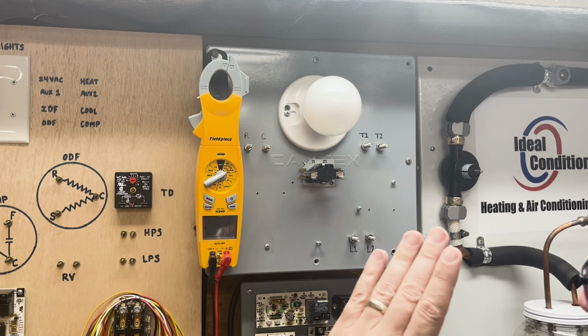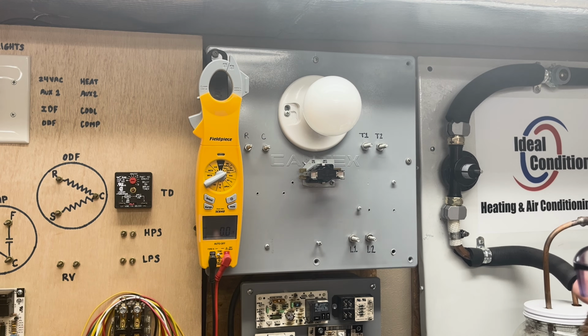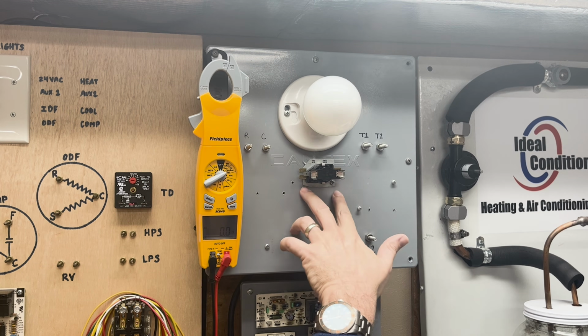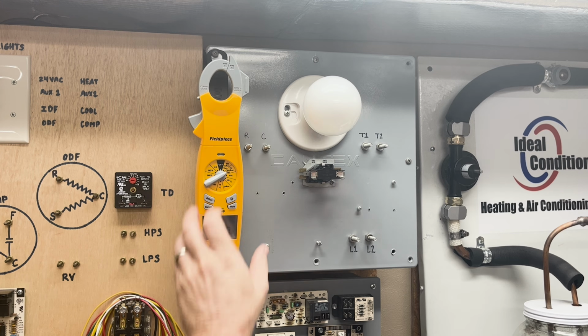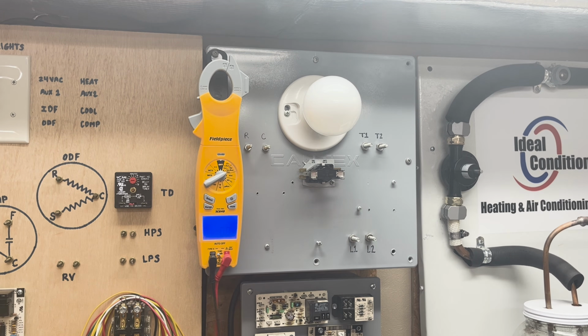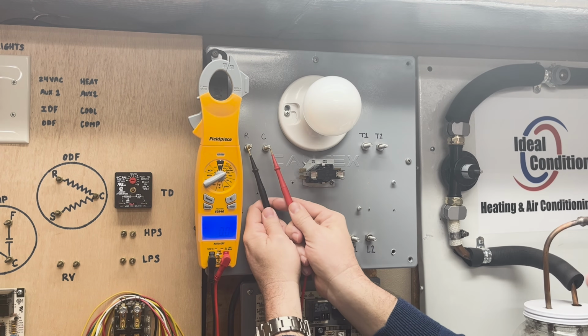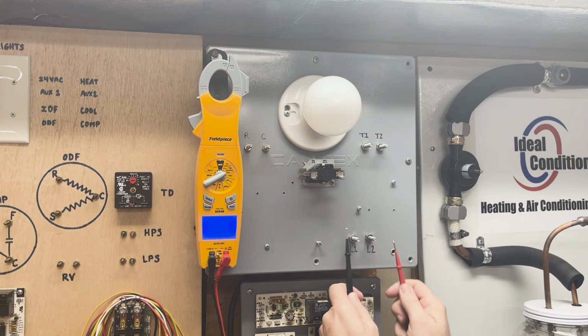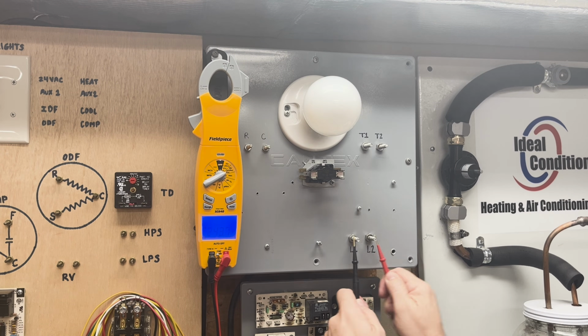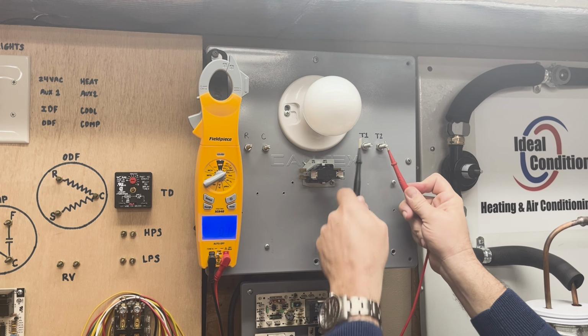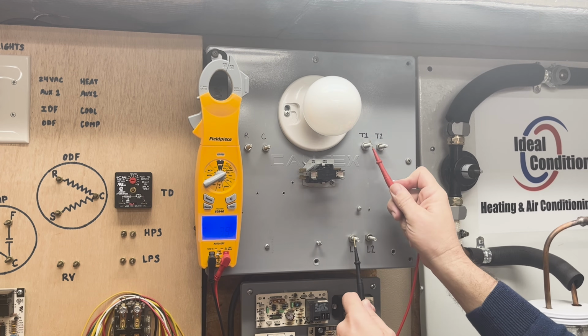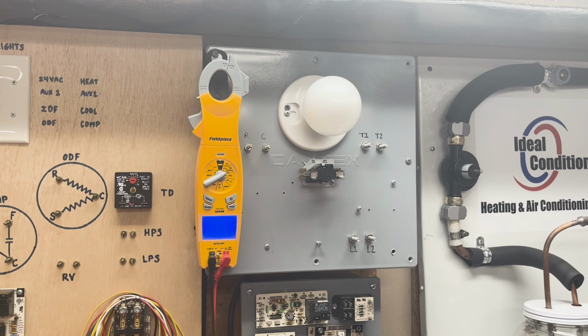However, in the Cantex box we have transformers and contactors, so you'll hear a clicking noise. When you hear that clicking noise, that's just the contactor engaging, bringing our load on. We have R and C, which is our 24 volt secondary control voltage, which we're going to utilize to control our relay. So we're going to go ahead and just demonstrate the power first. We'll come up to R and C, and you should see that we have 28 volts. Then we'll come over to L1 and L2, which you should see we have 243 volts. Obviously, T1 and T2 is going to have absolutely nothing, no matter what the combination, because we don't have a full two legs of power.